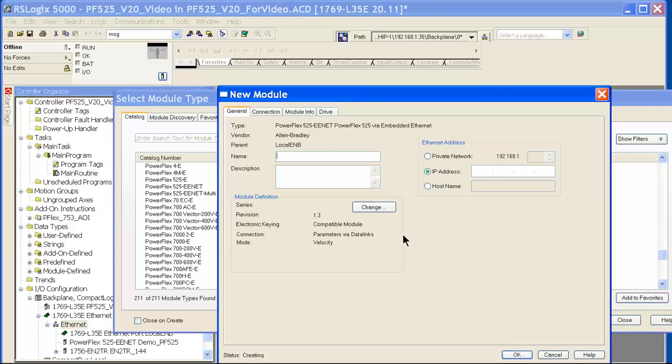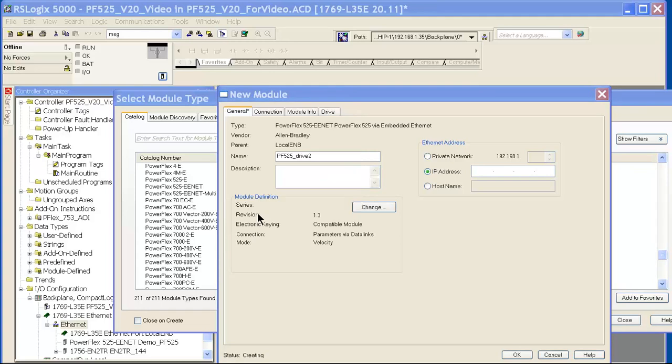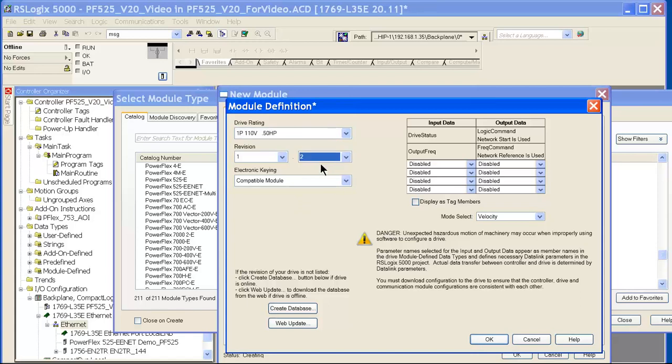Say create. Once this pops up, just like you do any other drive on Ethernet, just give it a name. Go to the change button and now we need to make sure that we have the same revision that the drive you bought is running at. Right now, the version I have is Rev 1.2, so I set that up.